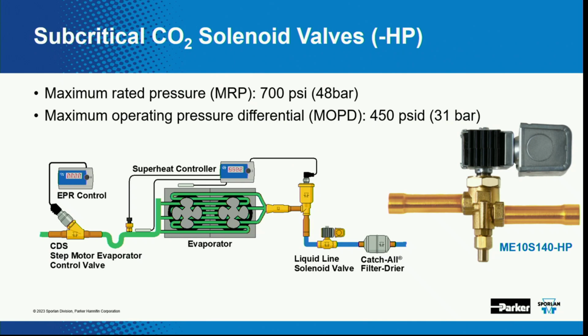Now, I'm showing here, and I didn't talk about this yet, a solenoid valve in series with an electric expansion valve. That's because if you have the system shut off, if you lose power, let's say, the stepper motor valve will stop wherever it is. If it's at 20% open when it turns off, it's going to stay at 20% open. If it's at 70% open, it's going to stay at 70% open. But we really want to close the line so we don't have refrigerant continuing to move into the evaporator, and that's what the liquid line solenoid valve does. So that's where you just use our regular HP solenoids, and you can get that job done.